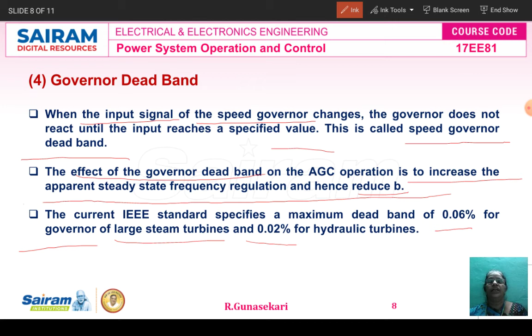The effect of the governor deadband is to increase the apparent steady state frequency regulation and hence reduce B. As per the IEEE standard, the maximum deadband specified is 0.06 percent for the governor of large steam turbines and 0.02 percent for hydraulic turbines. This is the governor deadband.